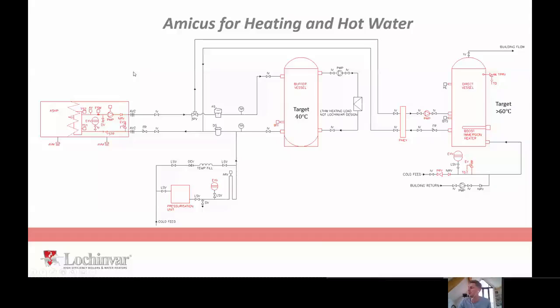Please bear in mind as well that, yes, my schematics do show immersion heaters, but those immersion heaters in any new build design will only ever come on if a heat pump breaks or it goes into a fault condition. So it's almost like your second point of failure, remember? That second point of failure for resilience, an immersion heater at 60 kilowatts would probably cost 1,200 quid. The 60 kilowatt air source heat pump would cost 25 grand. So from a residual, peace of mind point of view, it won't affect your carbon calculations, because your carbon calculations are based on a full heat pump system. And the only time it will come on is if the actual heat pump goes into maintenance.